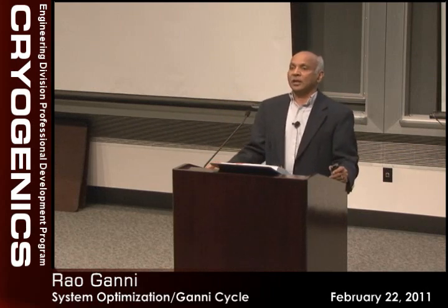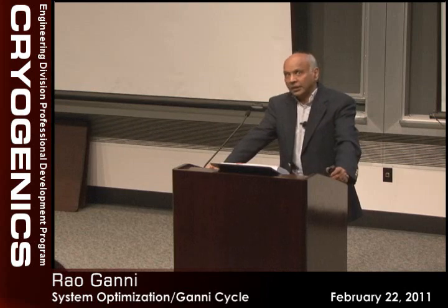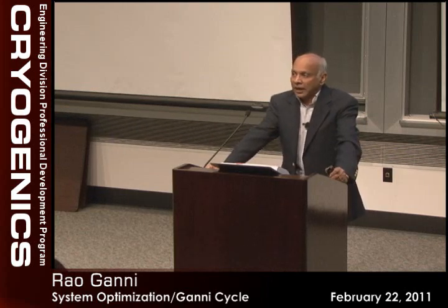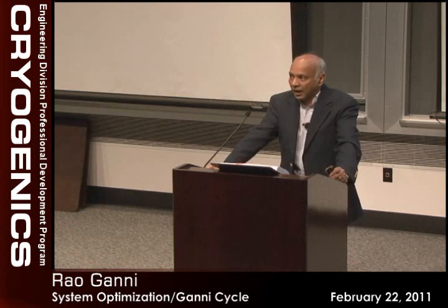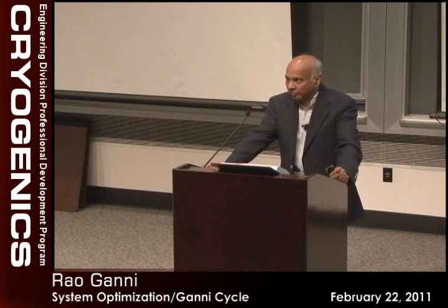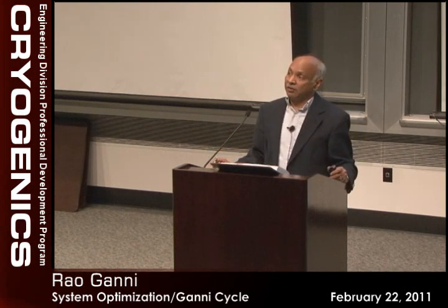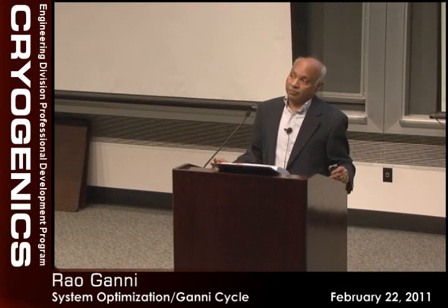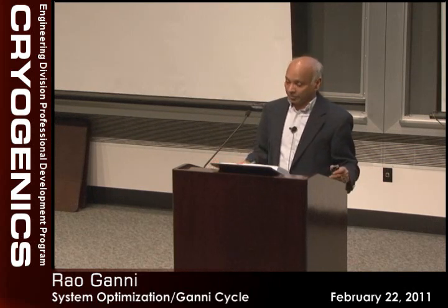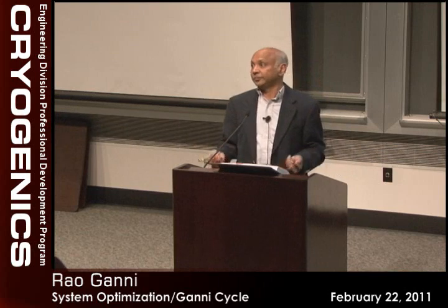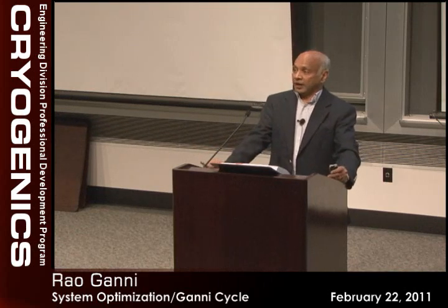What I'm trying to say is, when you go to these high effective, high efficient systems, every simple, small thing becomes a big issue. And you have to pay a lot of attention in designing the flow distributors, the distributor pressure drops, the core pressure drop, and all these things are very, very important and may not be that important in other industries. So when you push it to these levels, you have to be very careful.